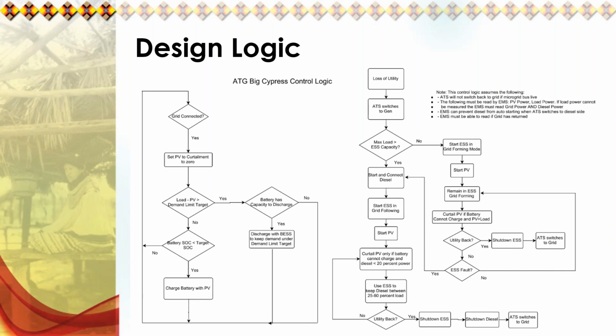We have requested that ATG revise this logic diagram so that when the grid is down, the battery runs the system for approximately 3 hours. After that, the generator kicks in, runs the facility, but also recharges the BESS. When the BESS reaches the optimum level, it takes over running the facility and the generator cuts off. So we do not anticipate the generator would have to run for more than 4 hours, and that is going to be a much better situation than having the generator run incessantly.